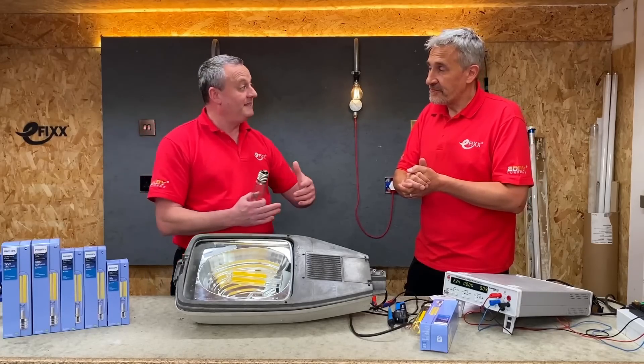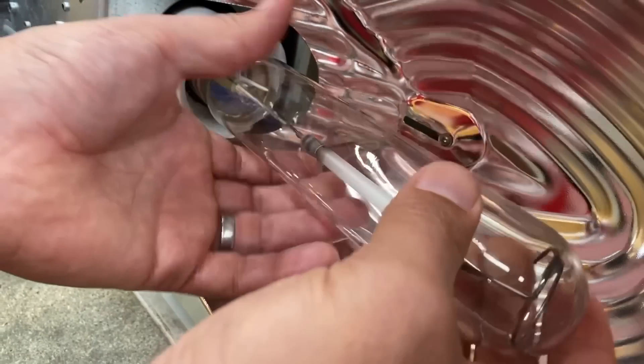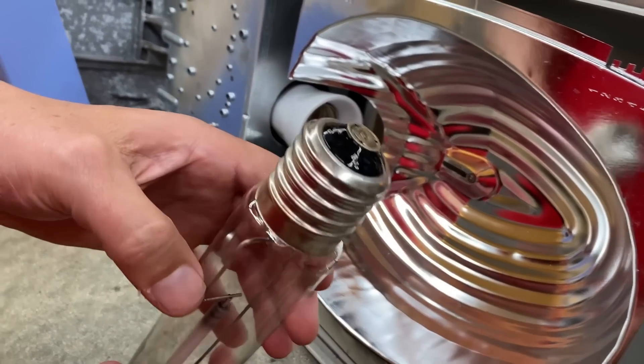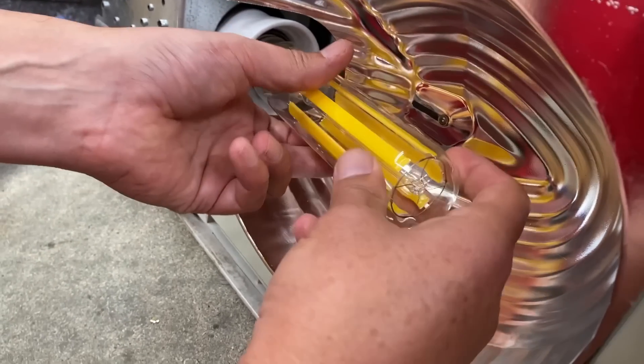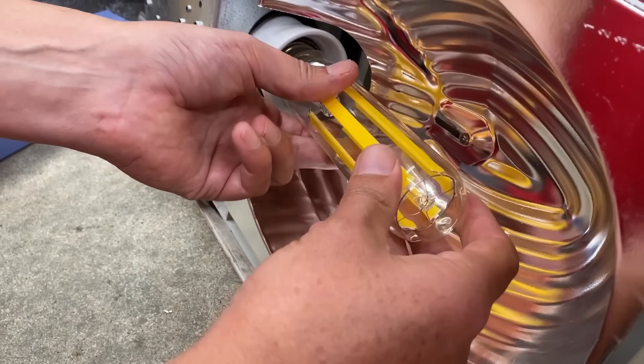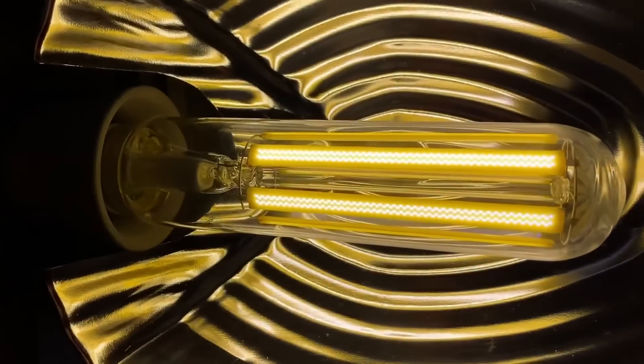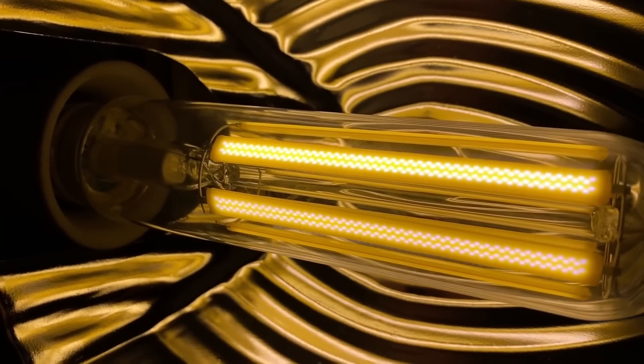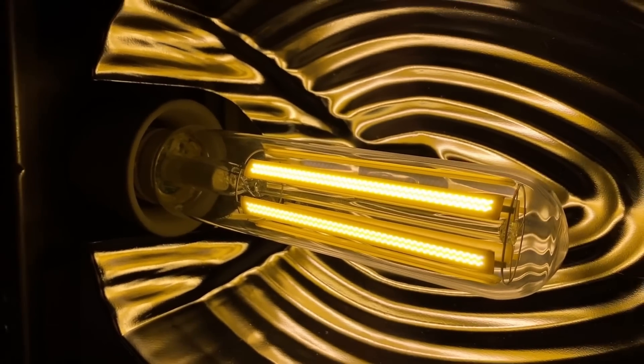You say quick win, so I'm expecting this to be a really simple process. What do I have to do to put one of these LEDs in? It's a drop-in replacement — just unscrew the existing SON-T lamp and screw this one into place, and you've already bagged a significant energy saving. In the case of this 100-watt lamp — the box says it's a replacement for 100 watts — we can go down to 40 watts straight away. When we made that direct replacement, we actually registered 45 watts on the instrument, so we went from 100 down to 45.